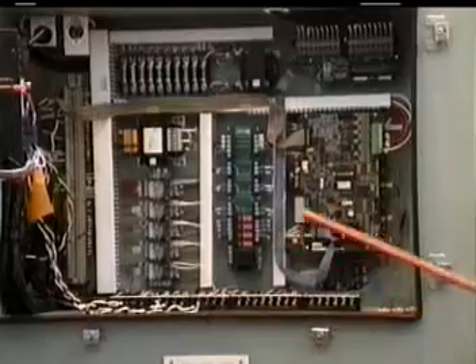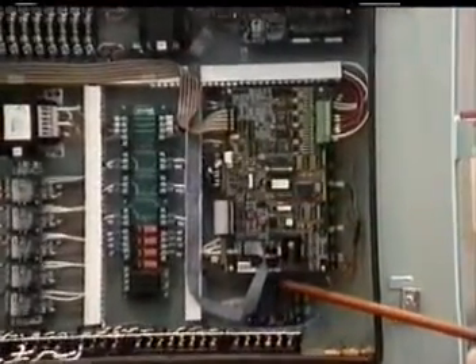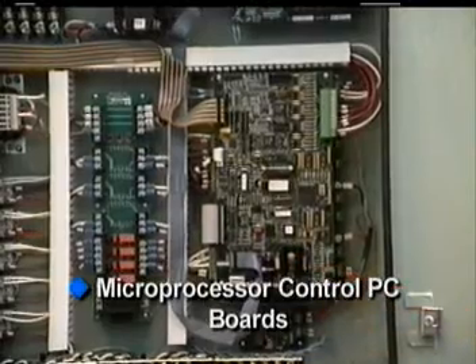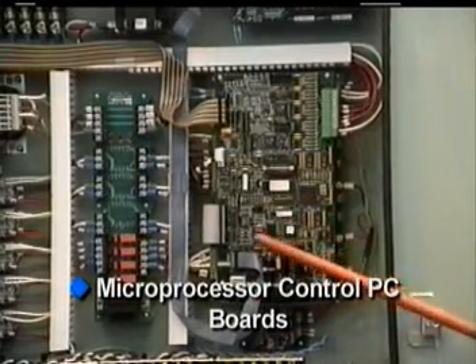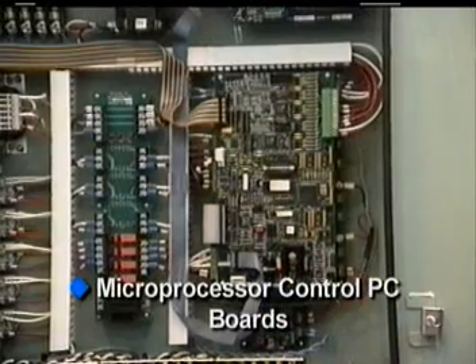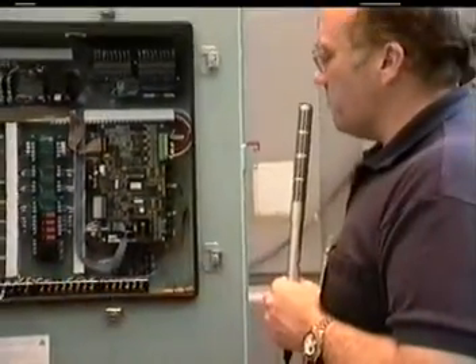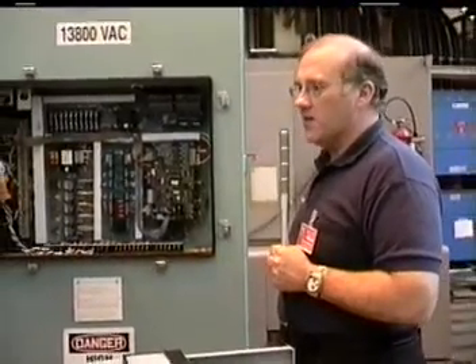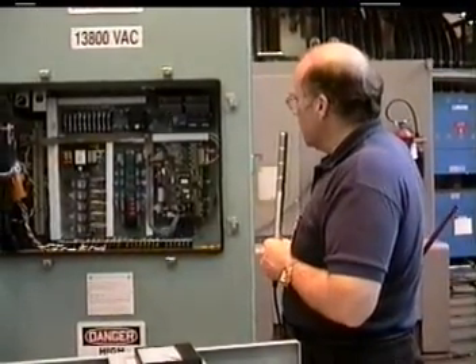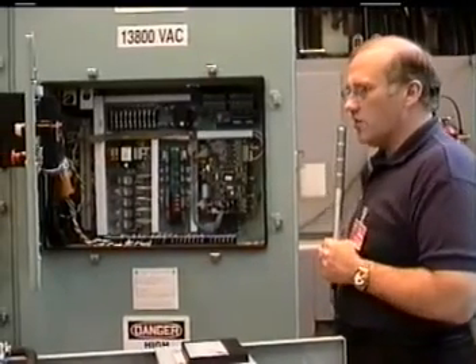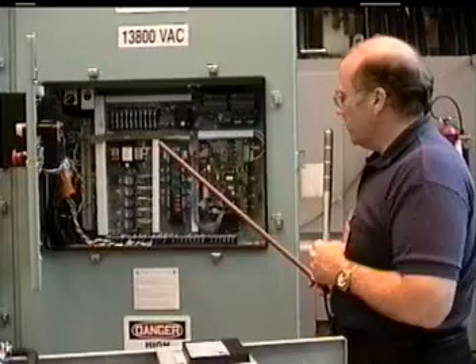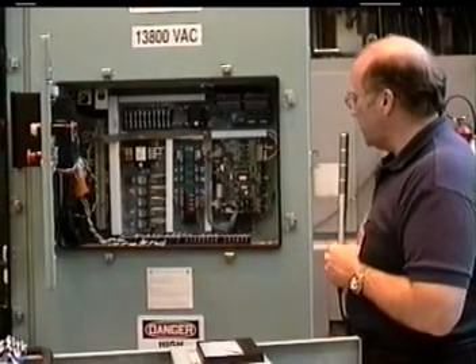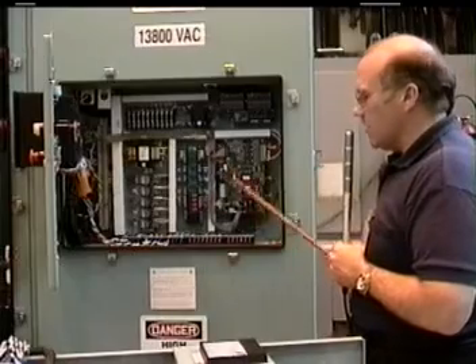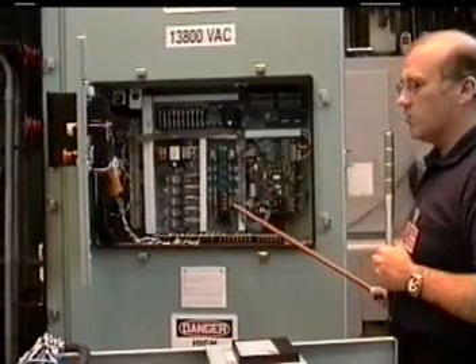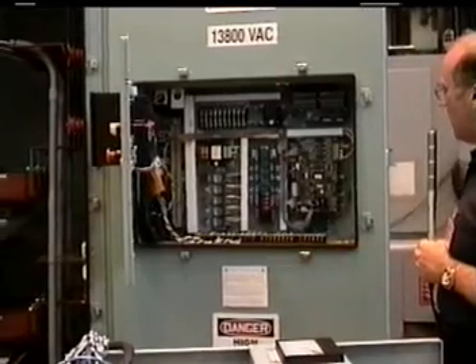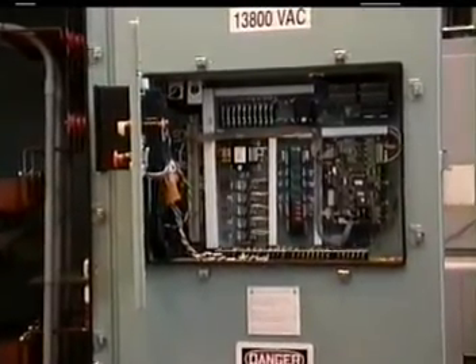The microprocessor section then consists of a CPU board as well as a power board. The CPU board is the heart of the system that contains the microprocessor code. It determines the programming sequence of events as to when to actually pick up an inline contactor, when to drop it out, when to fire the SCRs based on the settings from the display section of the low voltage section of the starter. It will then allow for current regulation from initial currents to maximum currents, and also the rate of rise in terms of the time from initial currents to maximum currents.